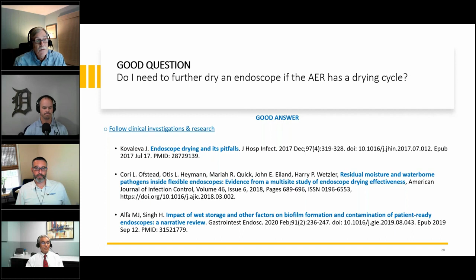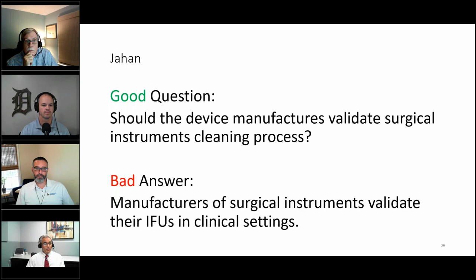And this is back to you, Jahan. The question being, should the device manufacturers validate surgical instruments cleaning process? Yeah, and we hear that a lot, the validation, and obviously the manufacturer of surgical instrument, they believe that all the IFUs have been validated. And especially there's some assumption that they are validated, their IFU in the clinical setting. So if you go back to the next slide, we talked about before that obviously only 10% of entire medical devices are being approved by FDA. So some of them, for example, the 47% of class 1 or the class 2, they don't have to do any clinical trial. But let's look at what validate means.